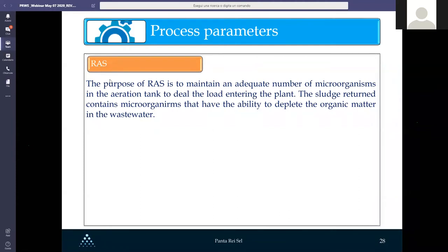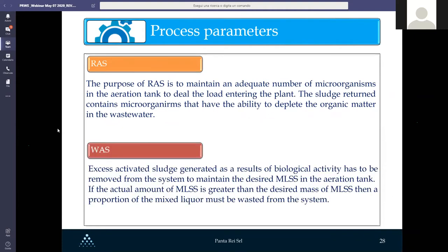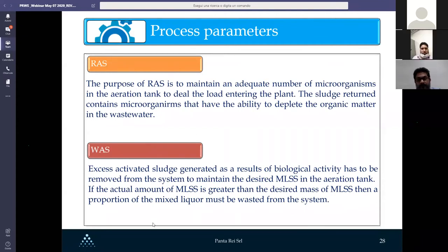The purpose of return activated sludge (RAS) is to maintain sufficient microorganisms in the aeration tank to handle the entering load. The sludge return contains microorganisms capable of depleting organic matter in the wastewater. Waste activated sludge (WAS) is the excess sludge that must be removed from the system when the actual amount of solids in the aeration tank is greater than the desired mass.